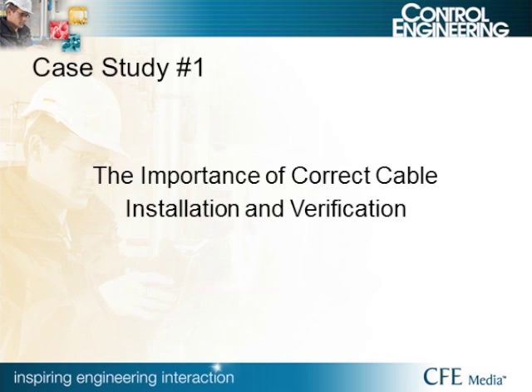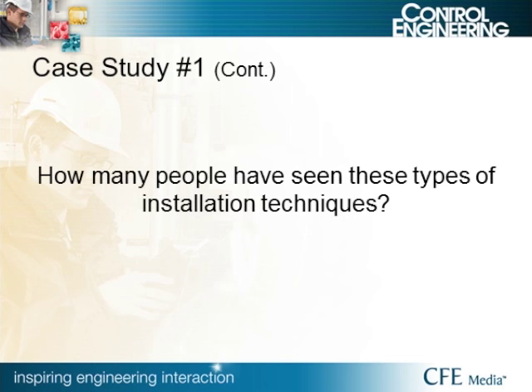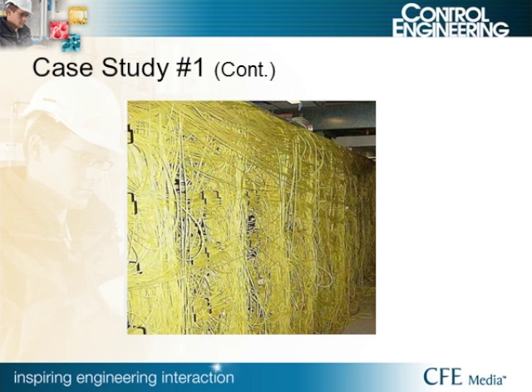On to the first case study: the importance of correct cable installation and verification. The next couple of slides show some interesting pictures — a lot of people will see something similar to this. This first one shows a cable installation that started out nice and organized, but kept growing until there was a wall of Ethernet cables. The whole point is, even when you start out with something good, you really need to stick with that standard and maintain proper segregation and cable structure.